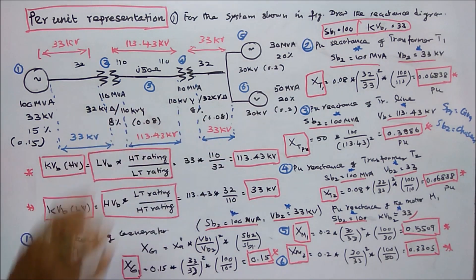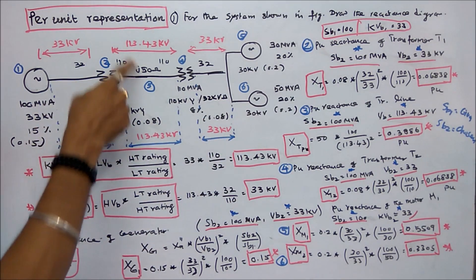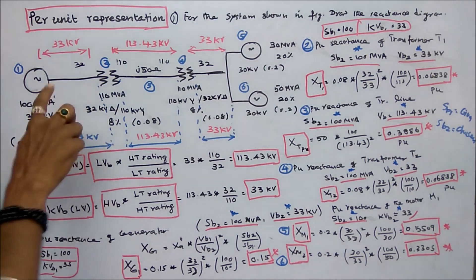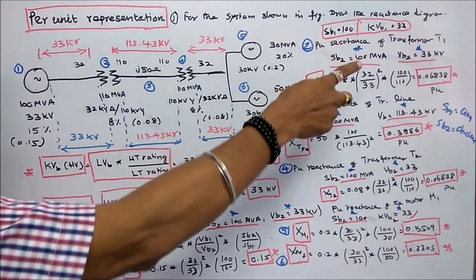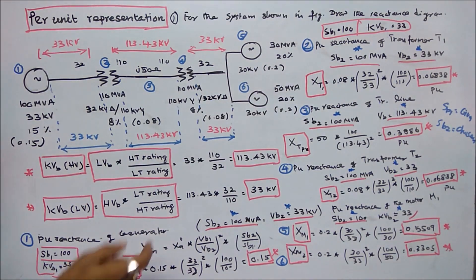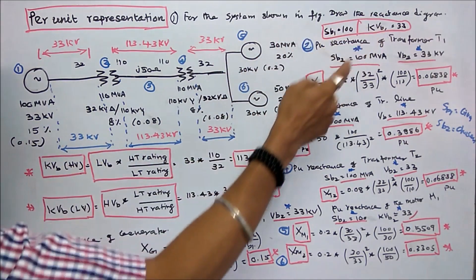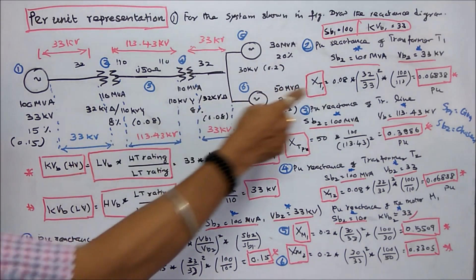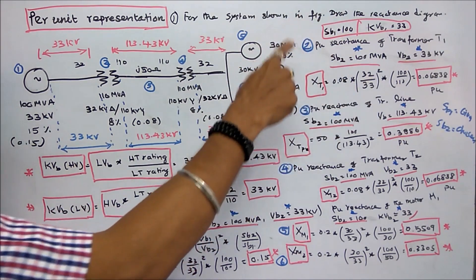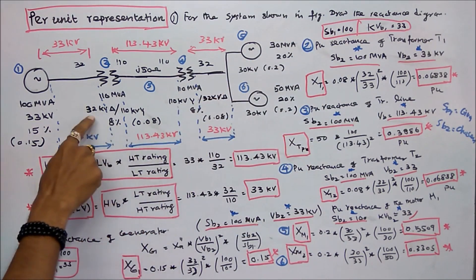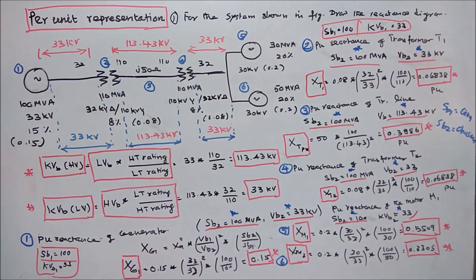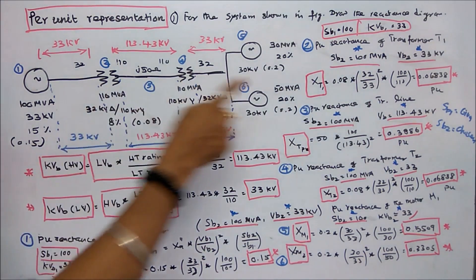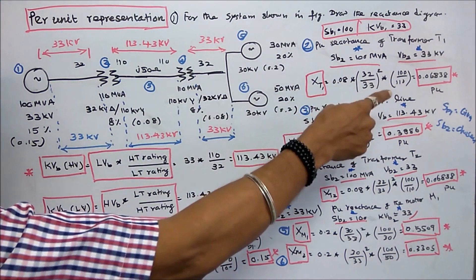The next is transformer T1. SB2 is 100 MVA, VB2 is 33 kV. Per unit reactance Xt1 equals given value 0.08 into (VB1/VB2) squared into (SB2/SB1). VB1 is given as 32, VB2 is 33, so (32/33) squared, times SB2 100 divided by SB1 110. That equals 0.06838.